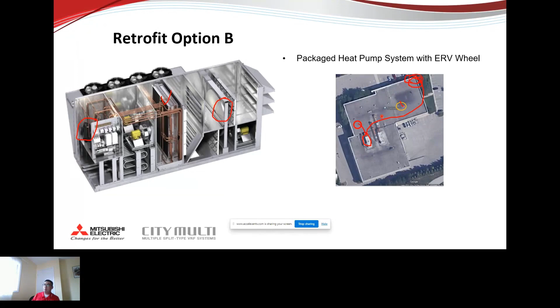Therefore, we are looking into utilizing VRF with zone-to-zone ERV. Because we are utilizing a VRF system that's capable of producing heating and cooling at the same time, everybody who has a thermostat can choose their own set point as well as one mode to be operating. So sometimes, instead of June 26th here in Toronto, let's imagine the end of October, early October, or end of September, somebody may need heating, somebody may need cooling. And we are able to achieve that heating and cooling at the same time. And actually, the more simultaneous heating and cooling you use, the better efficiency you have.